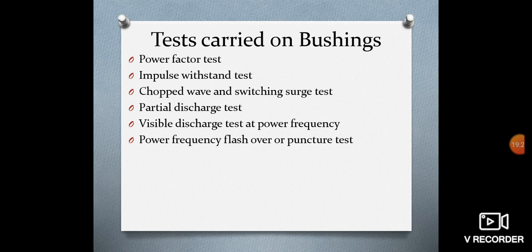We have the power frequency flashover or puncture test. The bushing is either immersed fully in oil or is installed as in service condition. This test is carried out to ascertain that the internal breakdown strength of the bushing is 15% more than the power frequency momentary dry withstand test value. So these are the tests. This is what it is all about, the tests carried out on insulators, cables and bushings.